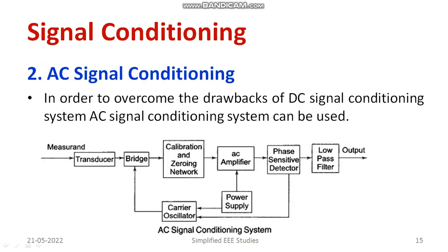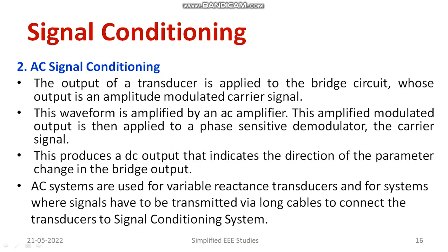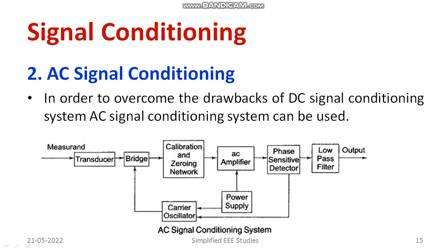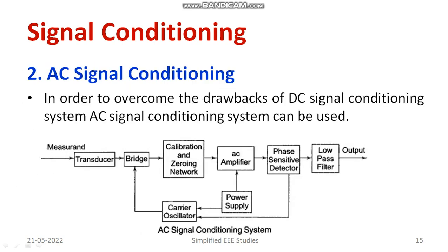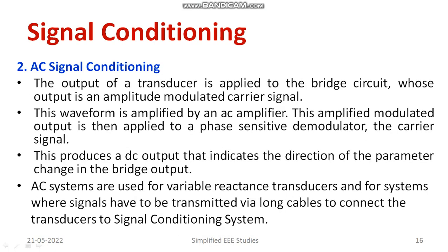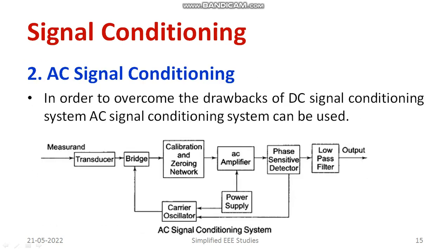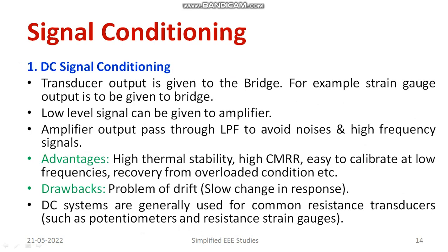The output of the transducer is applied to the bridge circuit, whose output is an amplitude-modulated carrier signal. This waveform is amplified by the AC amplifier after passing through the calibration network. The amplified modulated output is then applied to the phase sensitive demodulator. So modulation and demodulation are taking place in this process.